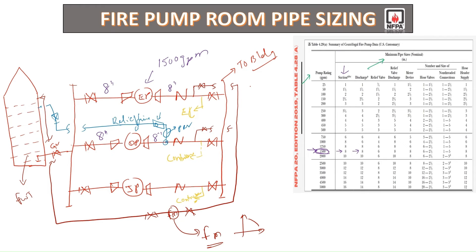For the jockey pump it will be different, since the capacity of the jockey pump is very less. The size of the jockey pump will depend upon the flow requirement, which may be 25 GPM or 50 GPM — it depends. You need to refer to NFPA 20 to select the jockey pump capacity. The discharge header will also be 8 inch based on this table, and the test line as well.